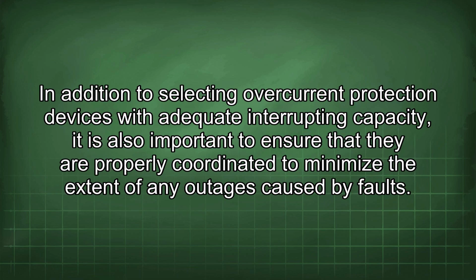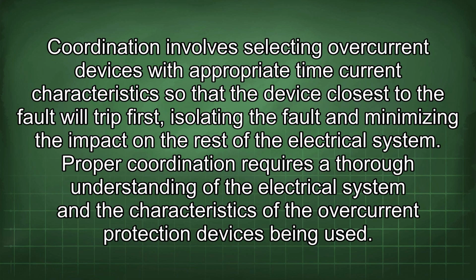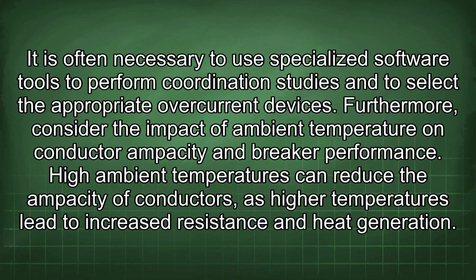In addition to selecting overcurrent protection devices with adequate interrupting capacity, it is also important to ensure that they are properly coordinated to minimize the extent of any outages caused by faults. Coordination involves selecting overcurrent devices with appropriate time-current characteristics so that the device closest to the fault will trip first, isolating the fault and minimizing the impact on the rest of the electrical system. Proper coordination requires a thorough understanding of the electrical system and the characteristics of the overcurrent protection devices being used. It is often necessary to use specialized software tools to perform coordination studies and to select the appropriate overcurrent devices.